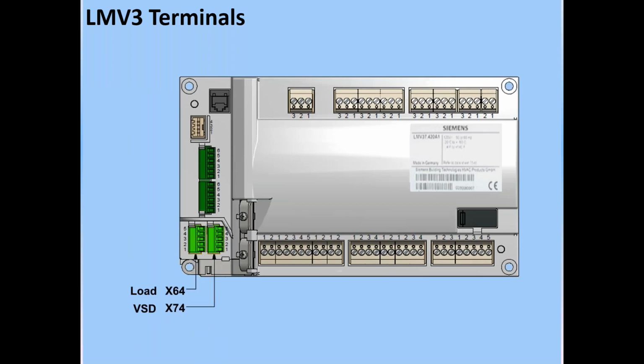Taking a look at the LMV3, we'll take a walk around on it. On the bottom left, you'll see I have highlighted the load terminal, X64. This is where the 4 to 20 milliamp would be put in to control the firing rate of the burner. Additionally, you could use Modbus or float bump, but this would be the load input terminal, 4 to 20 milliamp from a load controller, such as an RWF5 or any other load controller that you choose. Additionally, X74 would be where you would put in your variable frequency drive connections, or in the case of a PWM, your PWM connections.